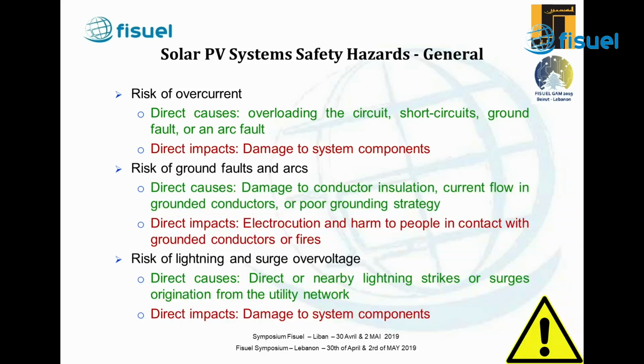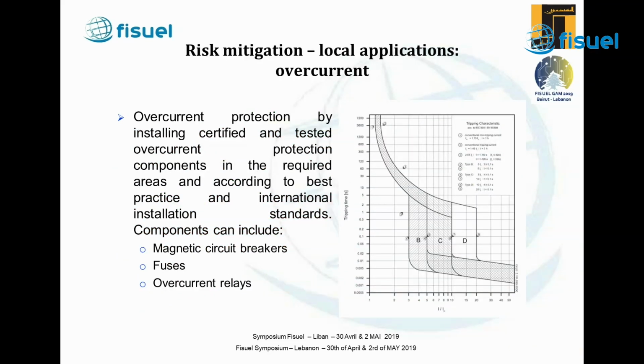Now, to cater for these risks and to answer them in an appropriate manner, for the local projects and installations that the UNDP did, we reverted to international standards, international codes, and international best practices in order to make sure that the solutions we're implementing and the projects we're doing are up to scale and as safe as possible. We did risk mitigation for these main safety risks. Overcurrent is mainly dealt with by the installation of overcurrent protection components that can include circuit breakers, fuses, and overcurrent relays installed in accordance with international standards on the DC side and on the AC side. An important thing to mention is that the correct type of component should also be selected for MCBs, be it B, C, or D, for instance.